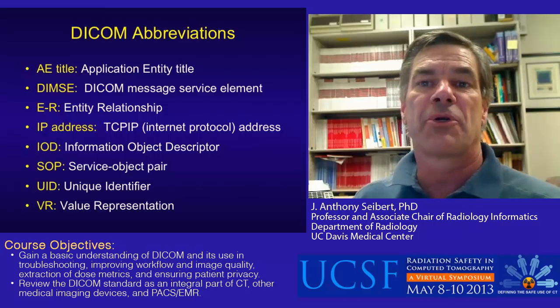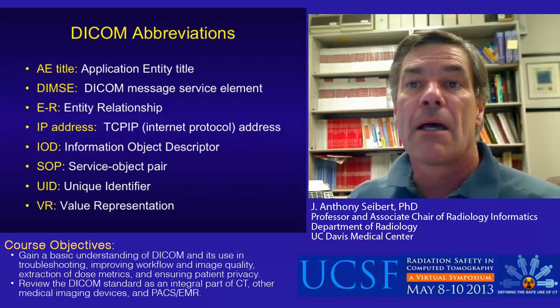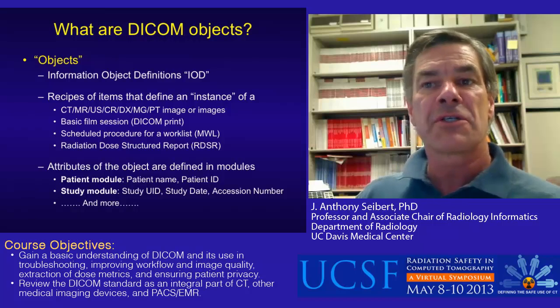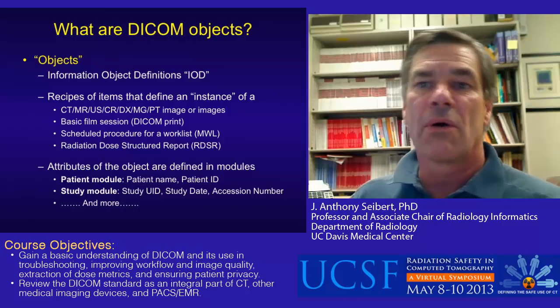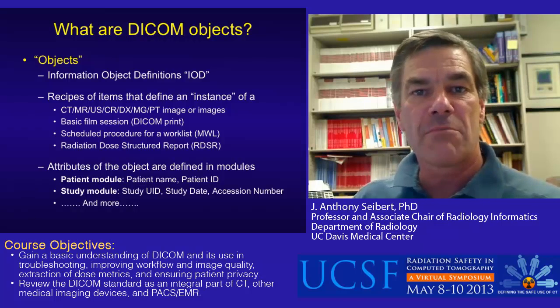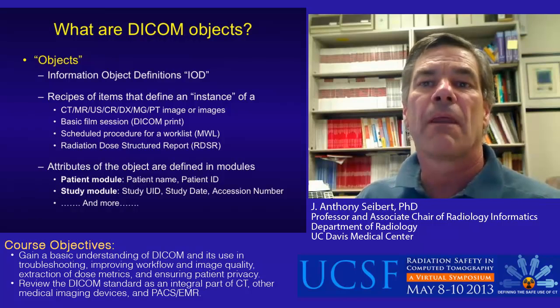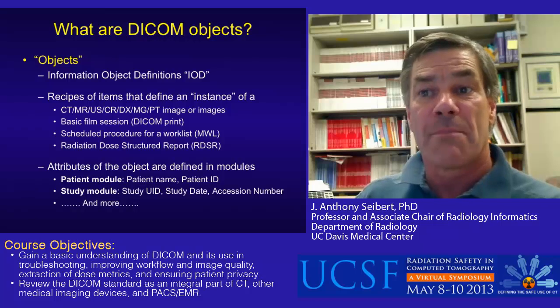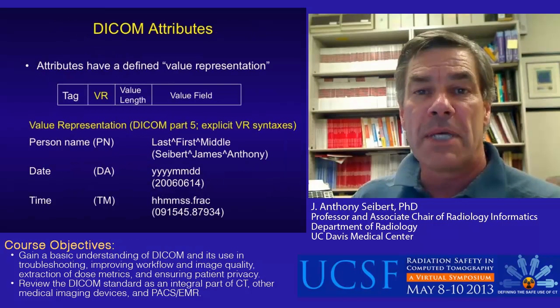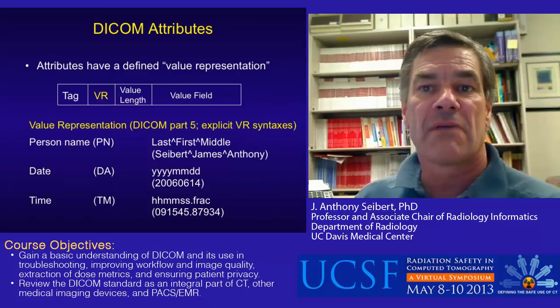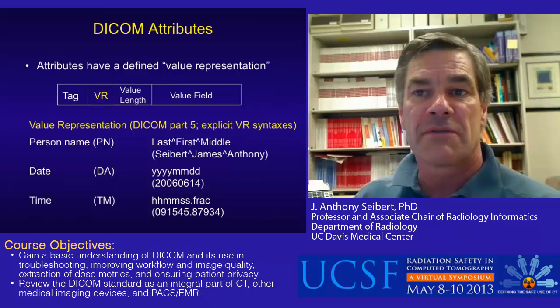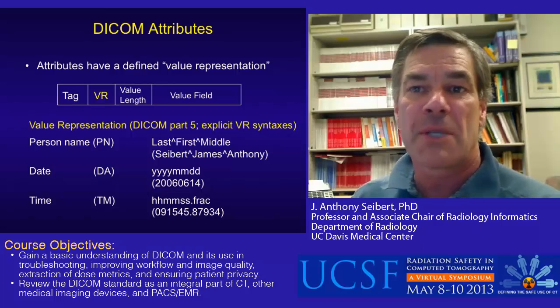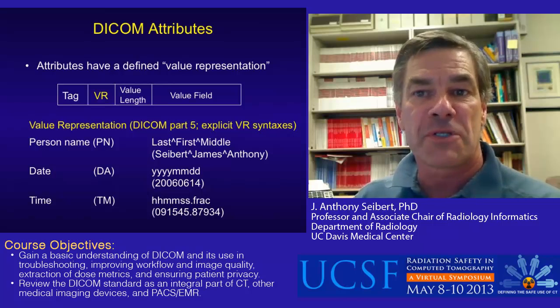IOD, Information Object Descriptor, is another important DICOM component. DICOM objects are recipes of items that define instances of an entity such as CT, MR, ultrasound, mammography, PET images, a modality worklist, or a radiation dose structured report. Attributes of the object are defined in modules contained in the DICOM metadata associated with the objects. In the metadata, DICOM attributes have defined tags, value representations, value length, and value field. Shown in this example is a portion of the patient identifier module, with data explicitly encoded and separated with caret separators for person name and explicit formatting for date and time.